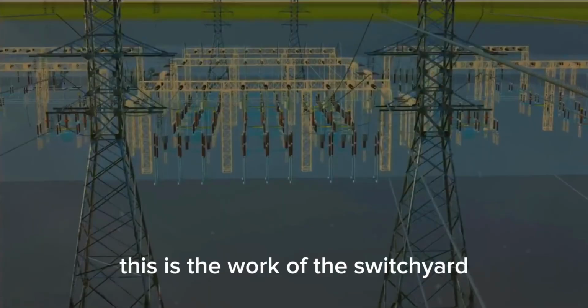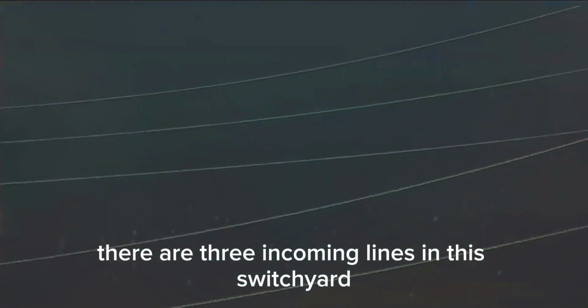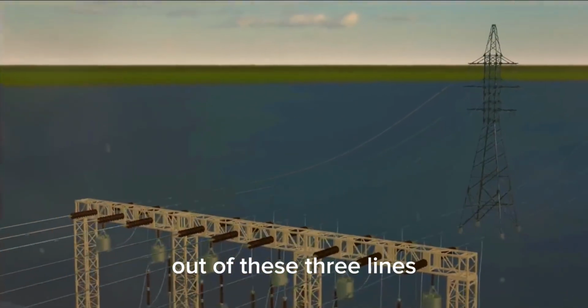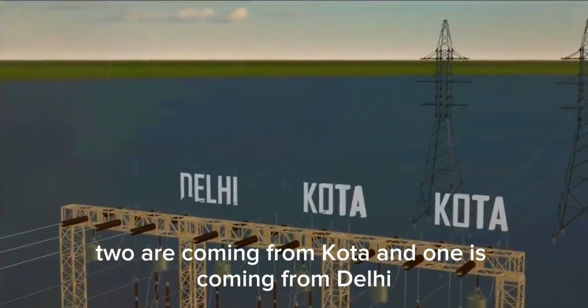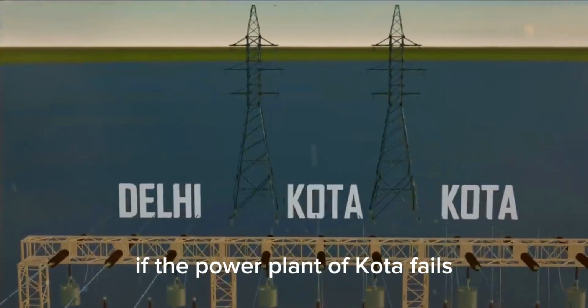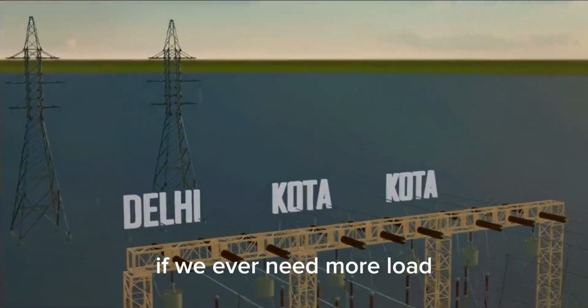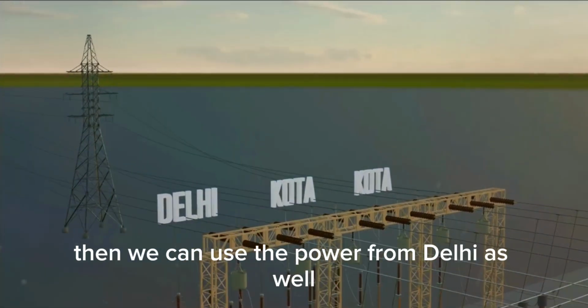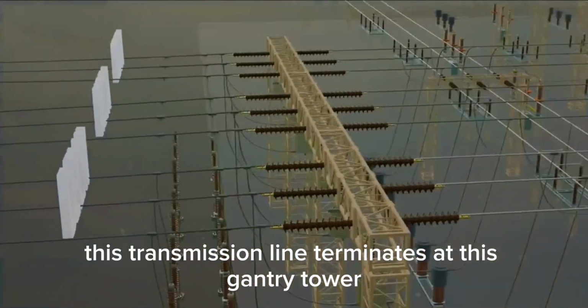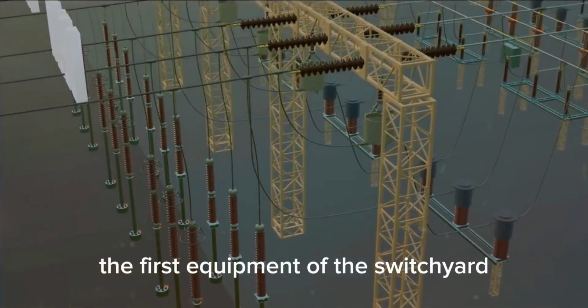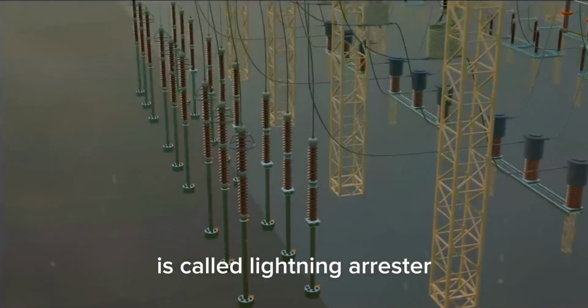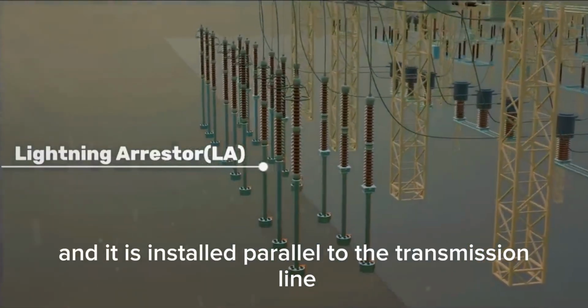This is the work of the switchyard. There are 3 incoming lines in this switchyard. Out of these 3 lines, 2 are coming from Kota and 1 is coming from Delhi. If the power plant of Kota fails, if we ever need more load, then we can use the power from Delhi as well. This transmission line terminates at this gantry tower. The first equipment of the switchyard is called lightning arrestor, and it is installed parallel to the transmission line.